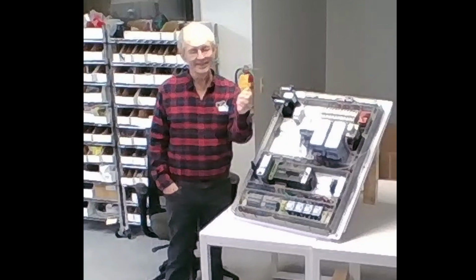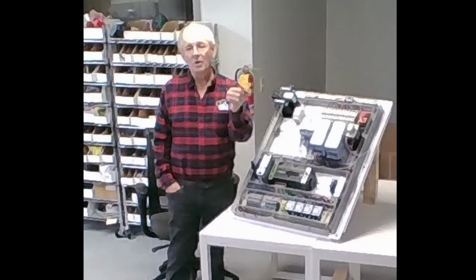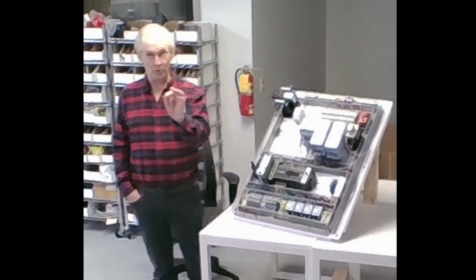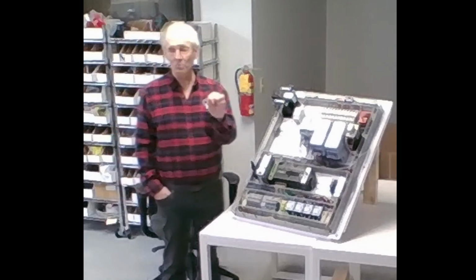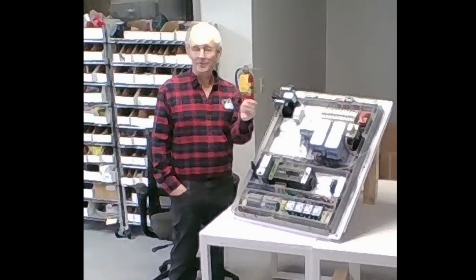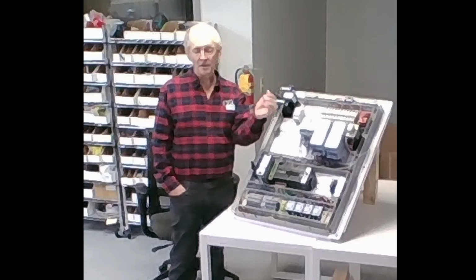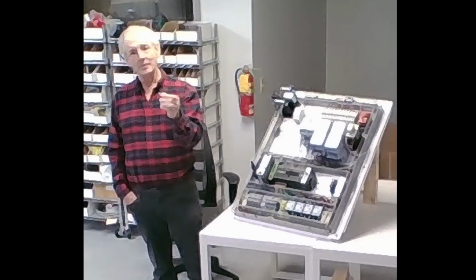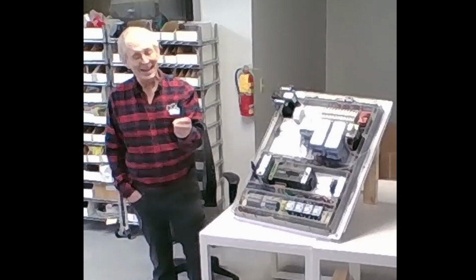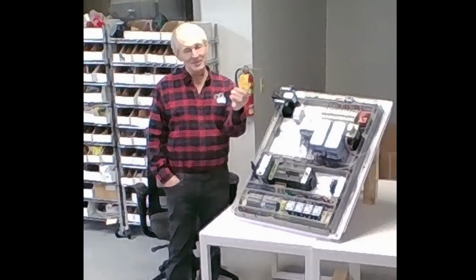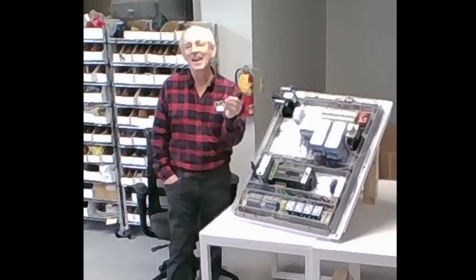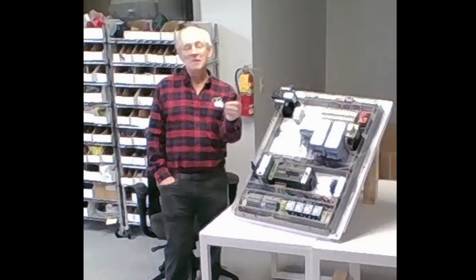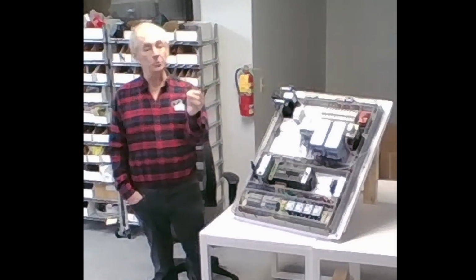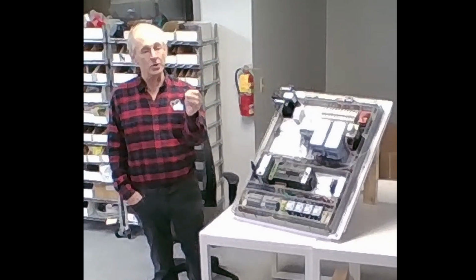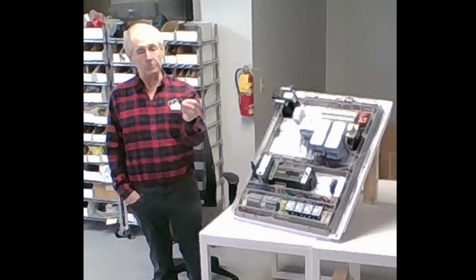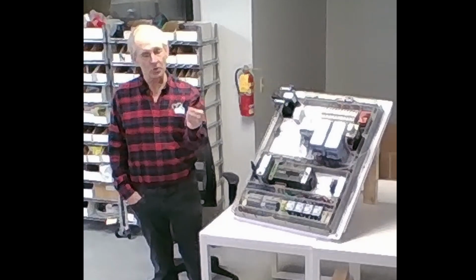What does that mean? It means it was an overload. In other words, the current was more than the fuse was rated to handle, all right? However, if I pulled that same fuse out and it's black, what does that mean? It means there was a high voltage, a high current surge. It vaporized the thing because it was a real high current.